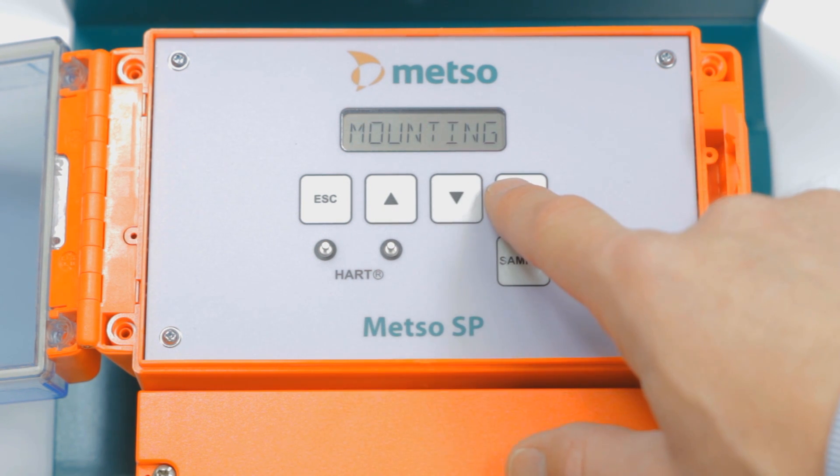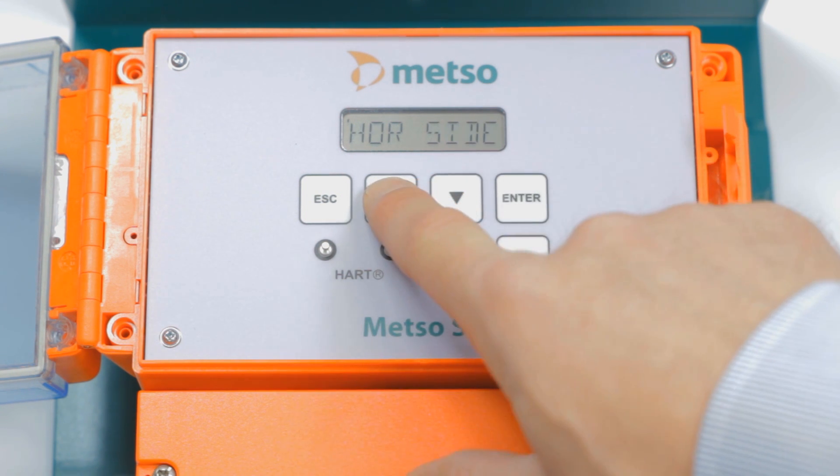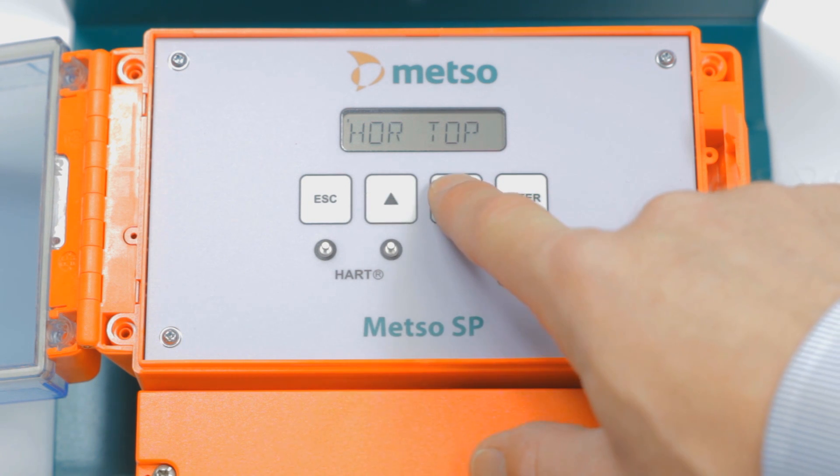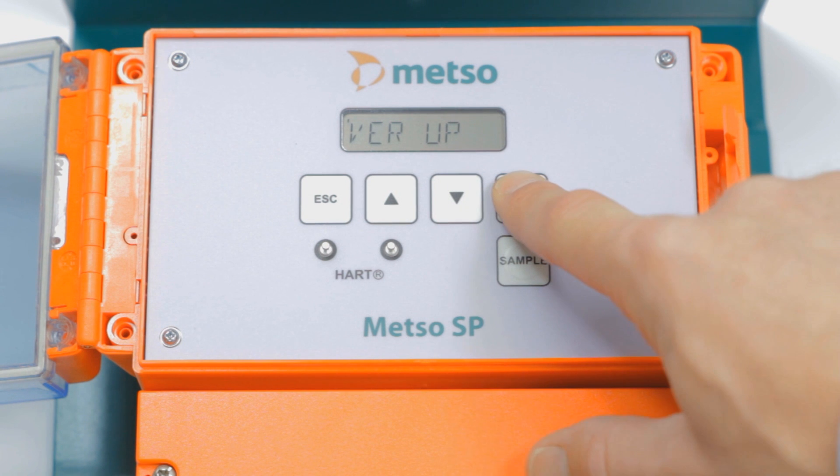Mounting, very important. If we hit enter, it's vertical up. There are other options. For example, horizontal side, horizontal top, depending on the mounting of the SmartPulp in the pipe. In our case, we're in vertical up, so we accept that.